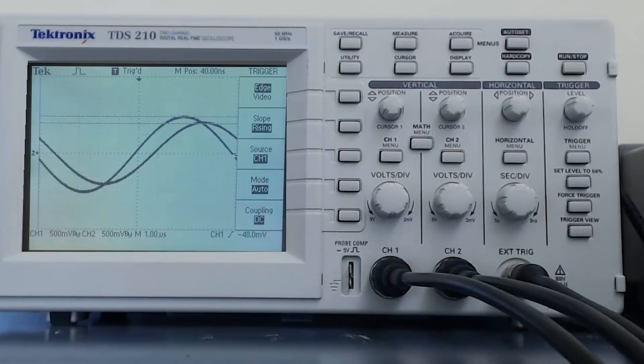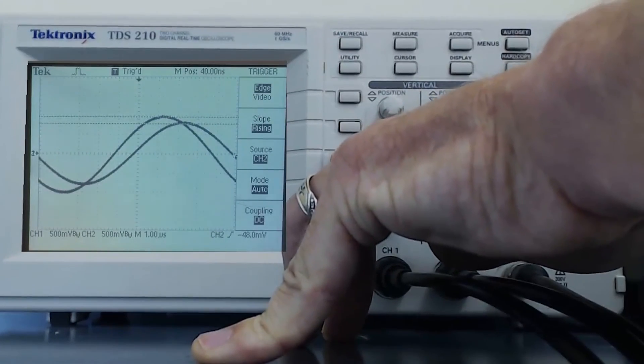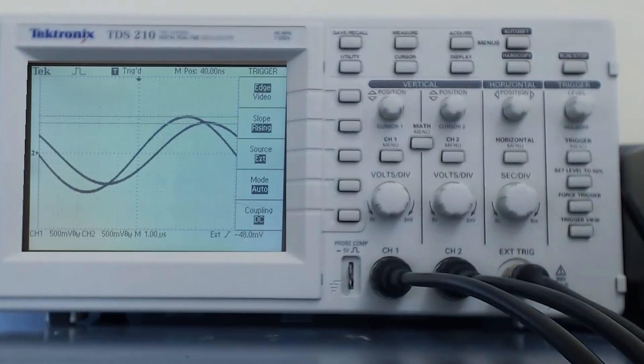For that, I will use a BNC cable to connect the sync to the external trigger. To use the external trigger, I go to the button next to Trigger Source on the oscilloscope screen, and select External. This allows the oscilloscope to trigger off of the very stable square wave the sync of the function generator outputs and renders any distortion of the output of the function generator irrelevant.